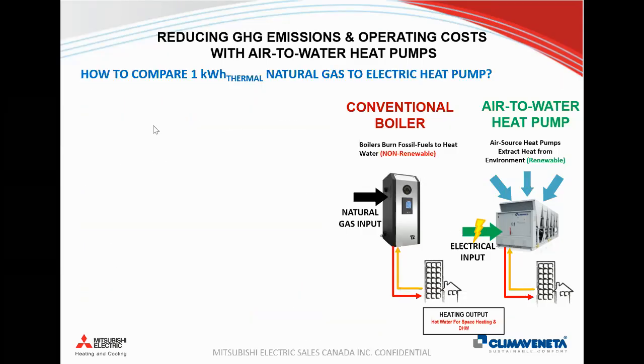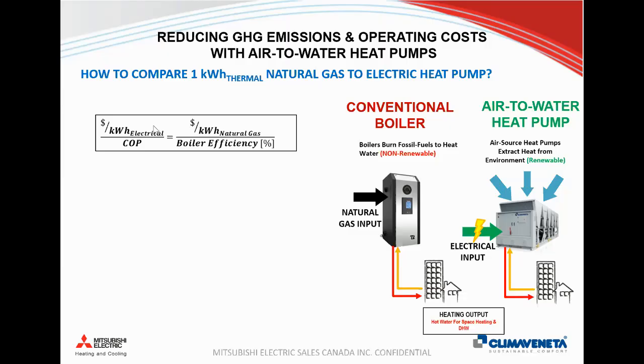So how do we directly compare the costs of 1 thermal kilowatt hour provided from either natural gas or a heat pump? A thermal kilowatt hour provided by a boiler is the same as a thermal kilowatt hour provided from a heat pump, so we can equate them. If we want to compare the dollars between the two, on the heat pump side, we look at how much we're paying for 1 kilowatt hour of electricity, which on average is around 11 cents per kilowatt hour in Ontario. If we divide that by the COP, that tells us how many dollars we're spending to provide 1 thermal kilowatt hour to the building. Similarly, for a gas boiler, we take our dollars per kilowatt hour of natural gas, whatever the cost is, and divide it by the efficiency to figure out how much it costs to supply 1 thermal kilowatt hour from the boiler.